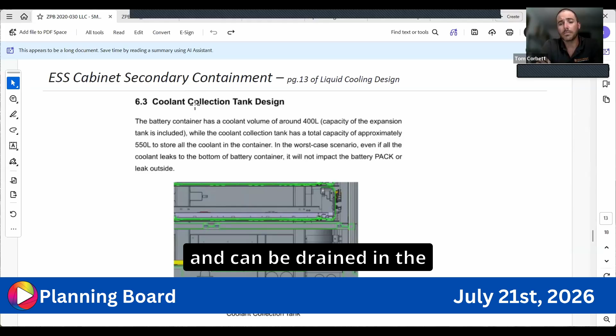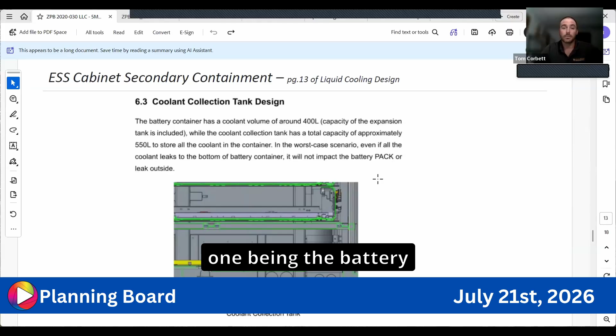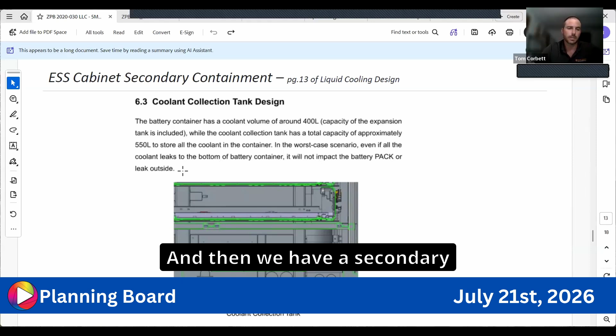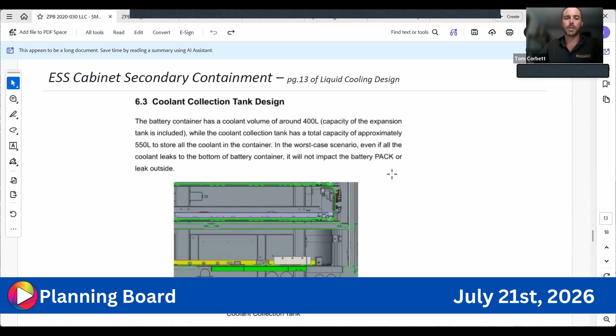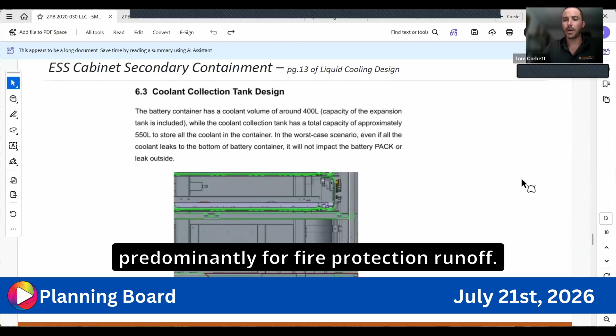That coolant collection tank is accessible from the outside of the container and can be drained in the event that there is a leak. So a couple different layers of secondary containment: one being the battery storage container itself having containment for the liquid volume that is housed inside and used to cool the system, and then a secondary containment system subsurface underneath the system itself, predominantly for fire protection runoff.